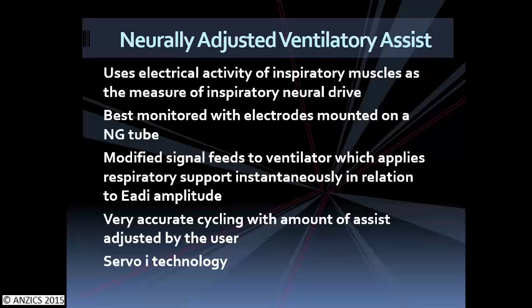And you can see there, can you see that clearly on the slide? If you're pressure triggering or flow triggering, no matter how sensitive your trigger is, there'll always be a delay before you initiate breathing in and before the ventilator gives you flow or pressure. So if you can trigger it electrically, as soon as the diaphragm starts to contract, it starts giving you support, and then it cycles off either on flow or when the electrical activity dies down to a certain point, it'll cycle to expiration. So the triggering on and the triggering off are neurally based. They're not based on flow or pressure.